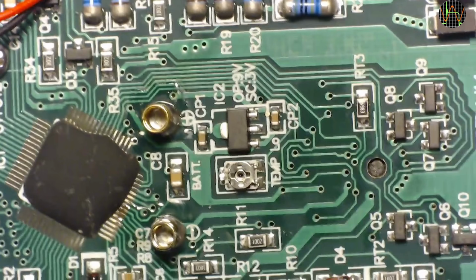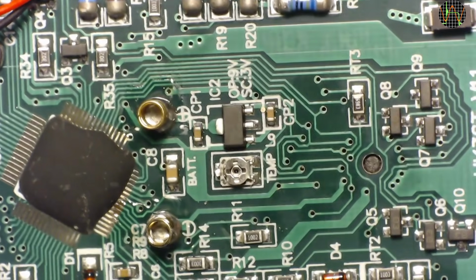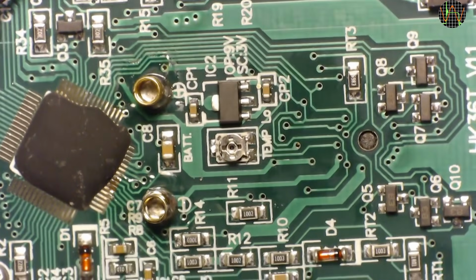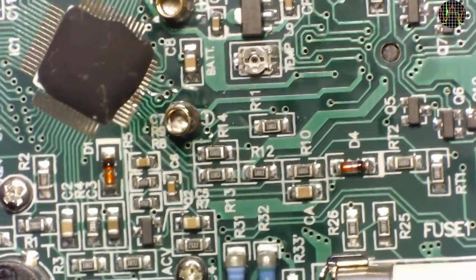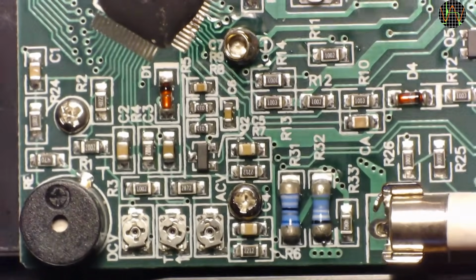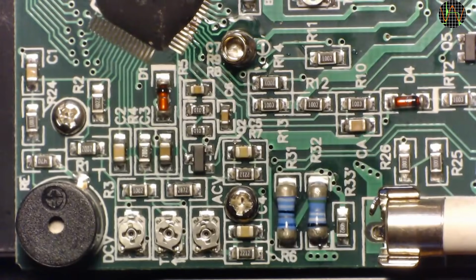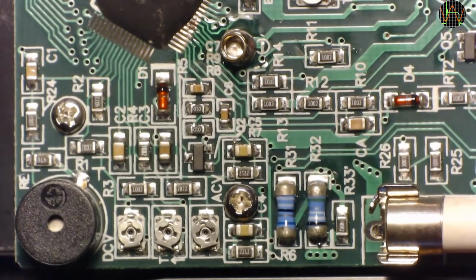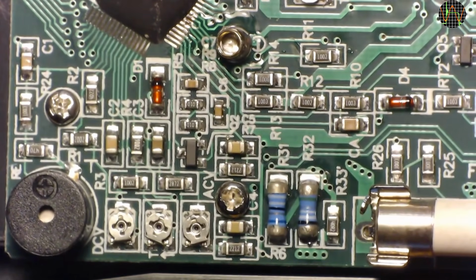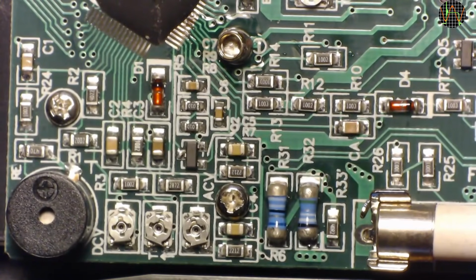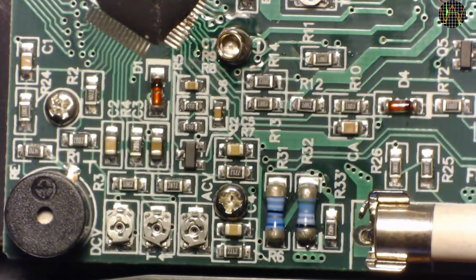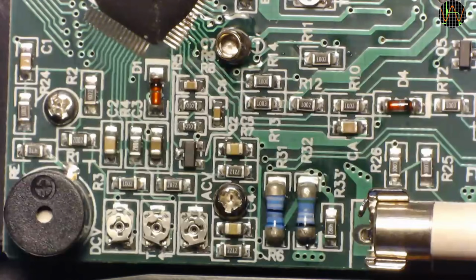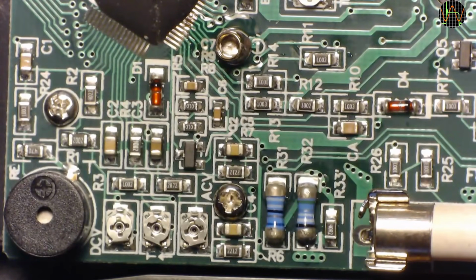Right in the middle is a trim pot marked temp. This will be for calibrating the cold junction temperature. Further below, right at the corner, we have a buzzer and then 3 more calibration trim pots. These are actually labeled DC volts, a T with an arrow, and AC volts. The meter certainly deserves praise for that, because that makes recalibration much easier.